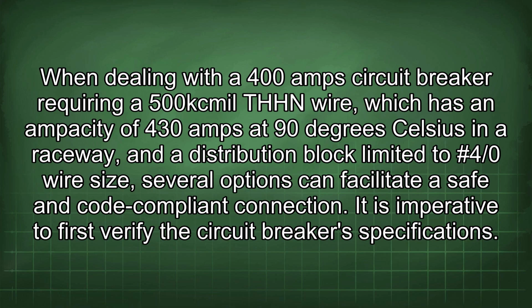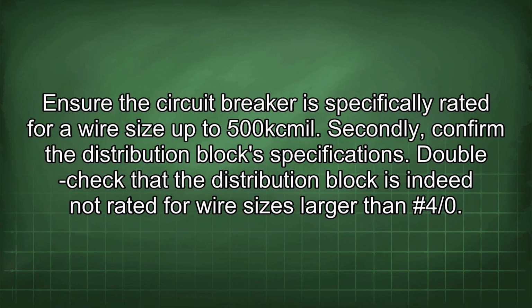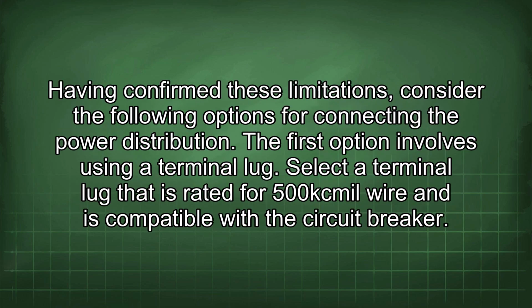It is imperative to first verify the circuit breaker specifications. Ensure the circuit breaker is specifically rated for a wire size up to 500 kcmil. Secondly, confirm the distribution block specifications. Double-check that the distribution block is indeed not rated for wire sizes larger than #4/0. Having confirmed these limitations, consider the following options for connecting the power distribution.